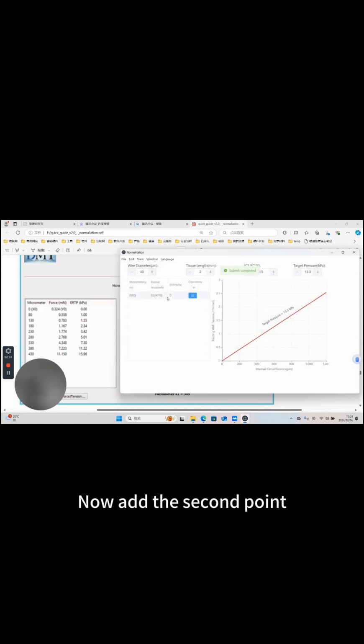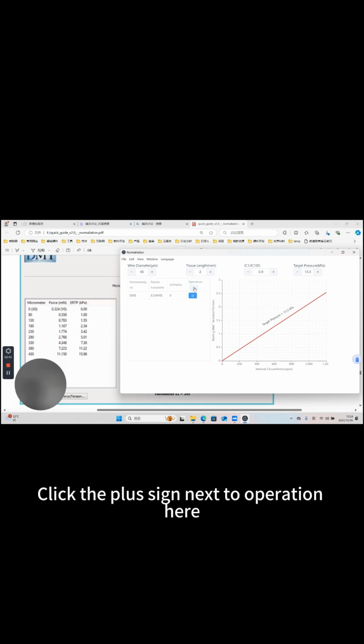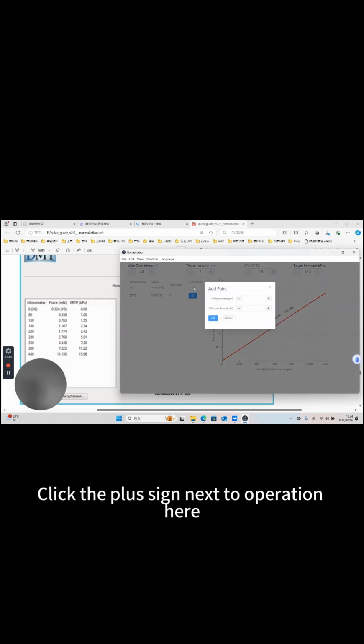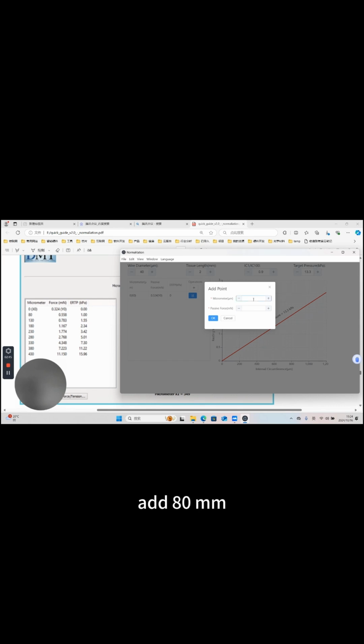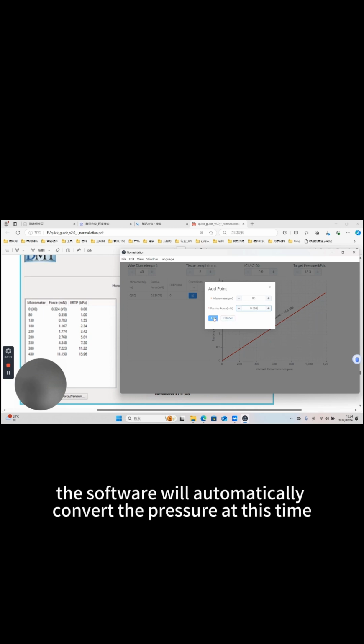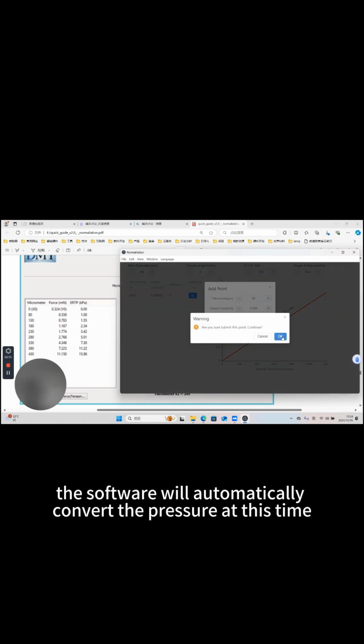Now add the second point. The second point is 80 micrometers. At 80 microns, its tension is 0.558. Click the plus sign next to Operation here. Add 80 microns, and the tension value is 0.558. At this time, the software will automatically convert the pressure at this time.